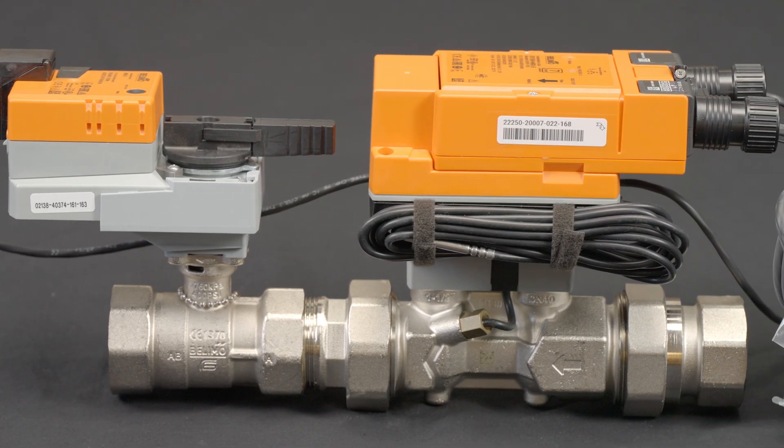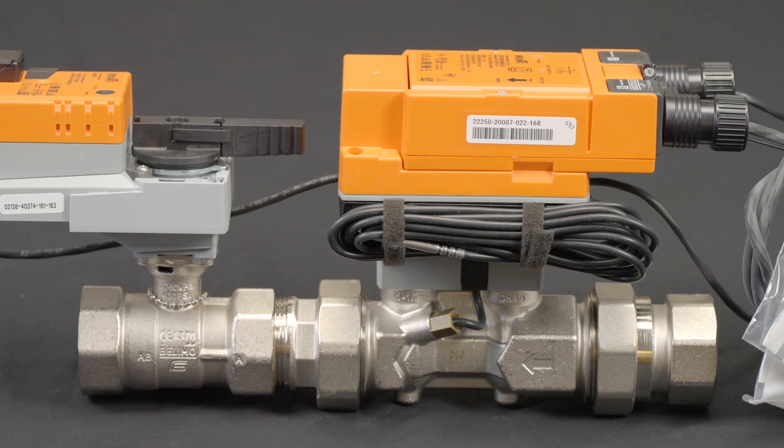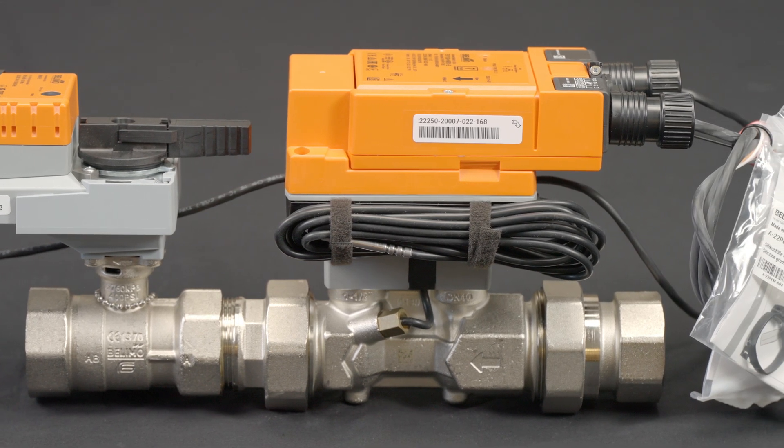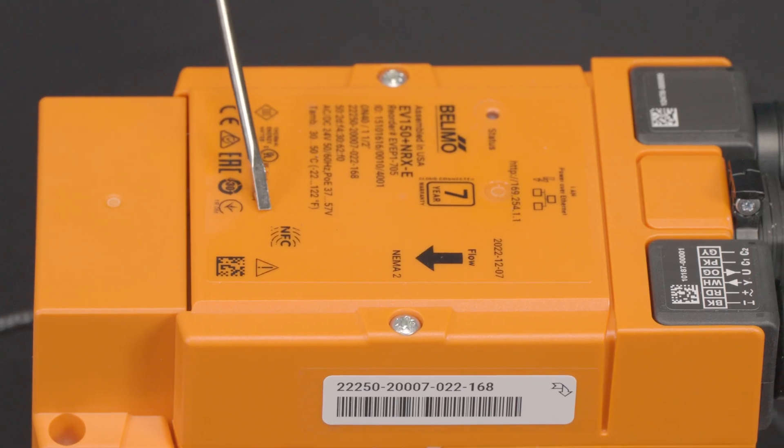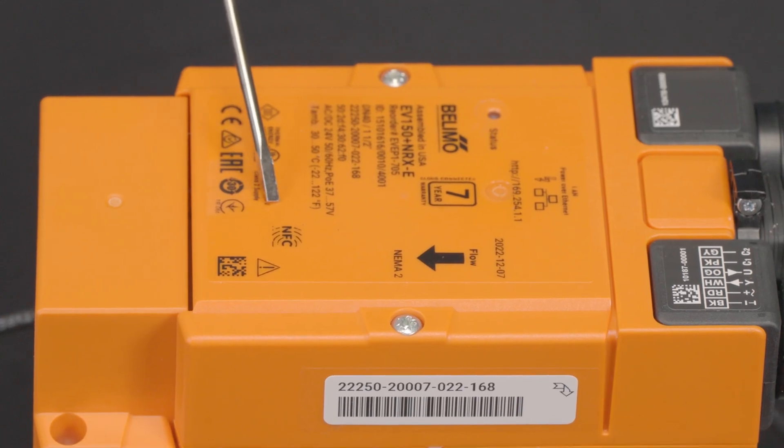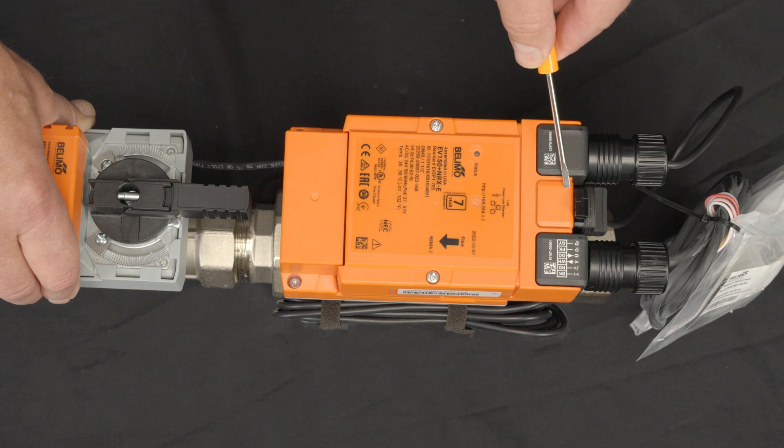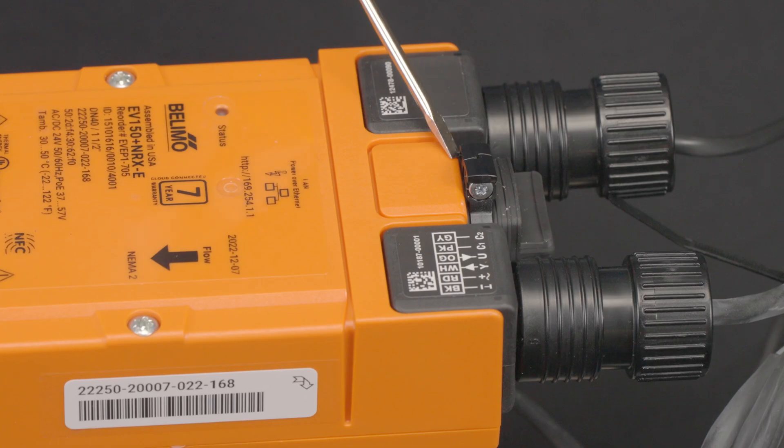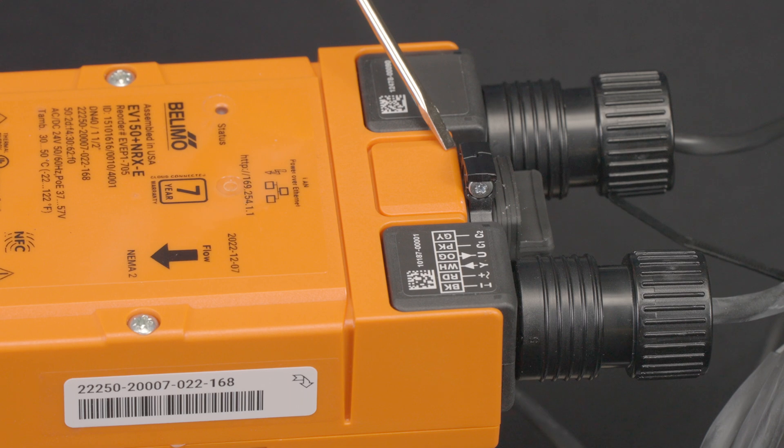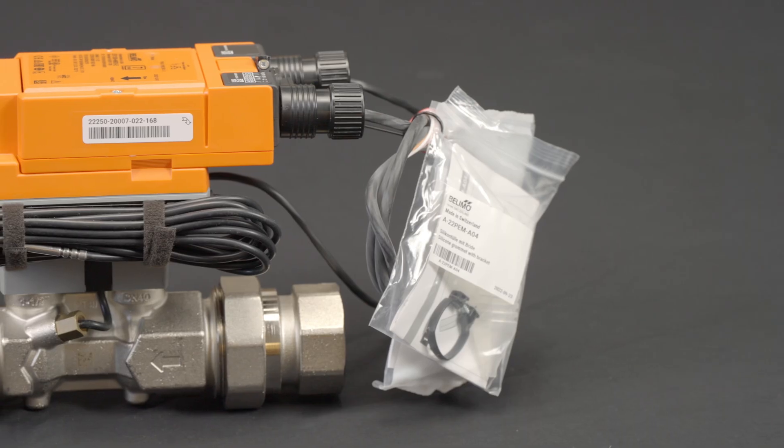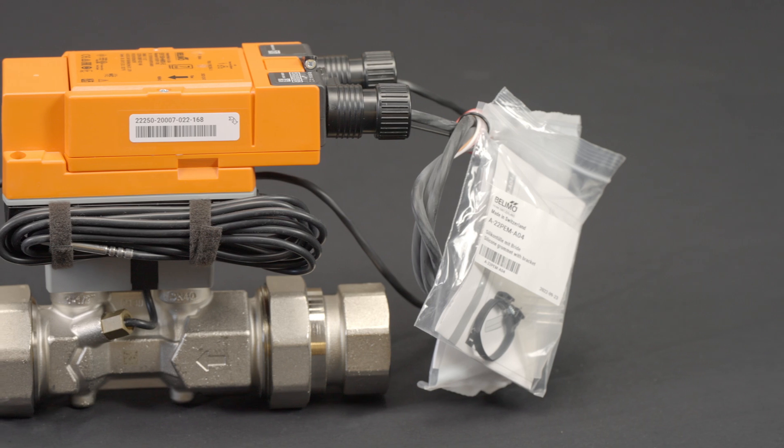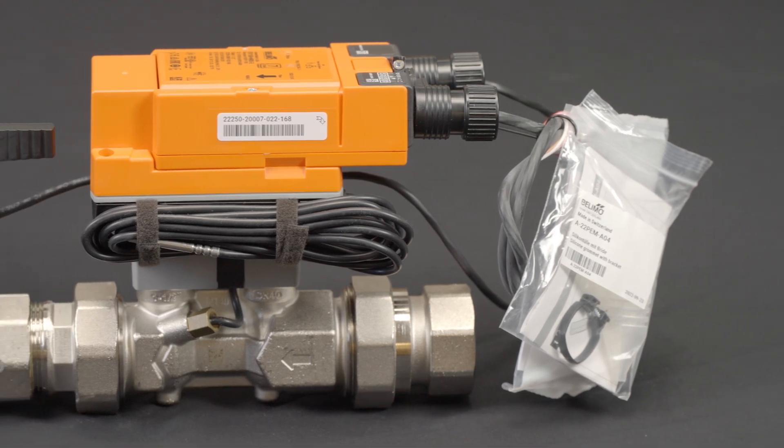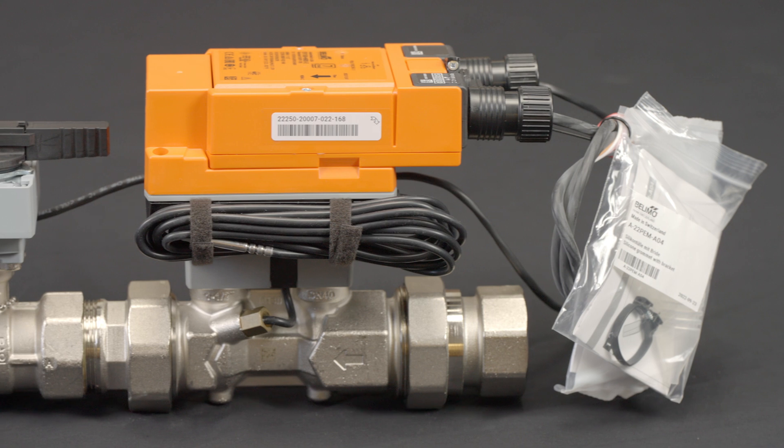It is important to note that older hardware versions of the Energy Valve do not support user installable firmware patches. You can identify an Energy Valve 4 by the NFC logo on the top of the sensor and the data cable connection will be on the sensor logic module. Older Energy Valve versions do not support NFC and the data cable will plug into the actuator. The thermal energy meter is a recent addition to our product family and will share the same hardware as the Energy Valve version 4.